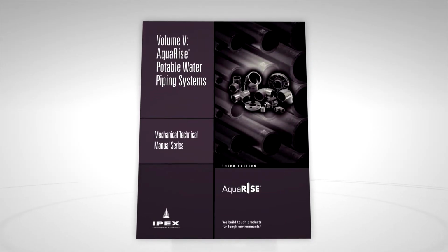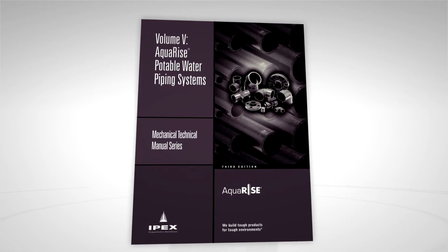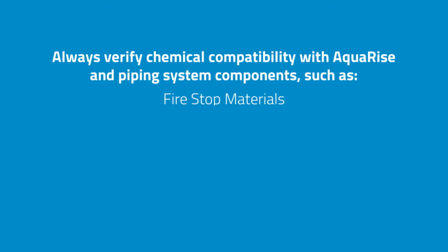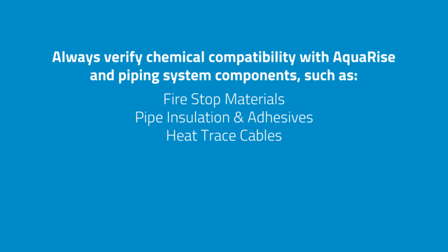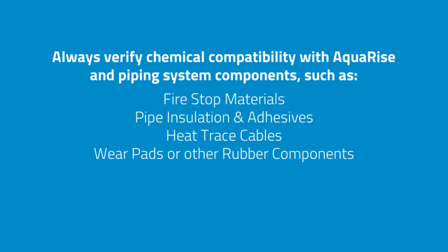Only system-compatible materials, including, but not limited to, solvent cements, caulks, and sealants, as noted in the technical manual, should be used in contact with the AquaRise system. Ensure chemical compatibility with AquaRise by checking with IPEX and the manufacturers of such common piping system components as fire stop materials, pipe insulation and adhesives, heat trace cables, wear pads or other rubber components, thread sealants.